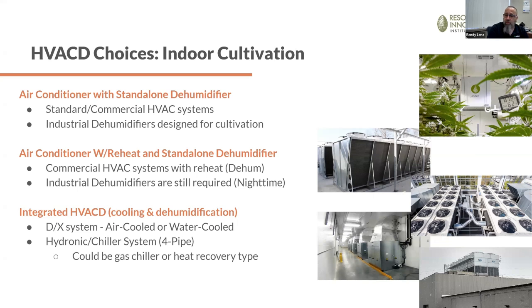You'll need to oversize that air conditioning to do that, adding extra tonnage because it has to run longer to reject the heat it put back in. But it does work. Typically you still need dehumidifiers. With this setup you can get pretty good dehumidification, maybe all of it, during the daytime hours with that air conditioner and reheat system. But at nighttime they can struggle because there's not a lot of heat to reject. When all the lights are off and a room that might only take a couple tons of cooling has a 40-ton air conditioner, it doesn't run long enough to provide enough reheat to dehumidify.